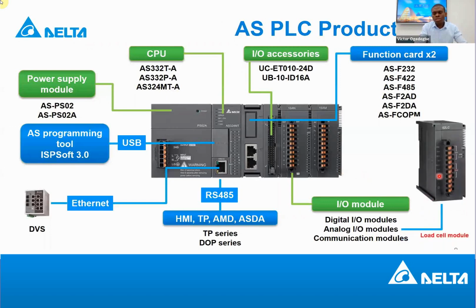The load cell module is basically an analog to digital converter. It takes the output from your load sensor and converts it to a digital value. Based on that digital value, you can control your machine and do what you want to do. So our focus today, the load cell module, is an analog module that you can use with the AS200 PLC or AS300 PLC.